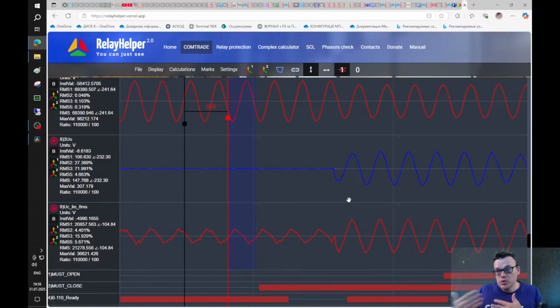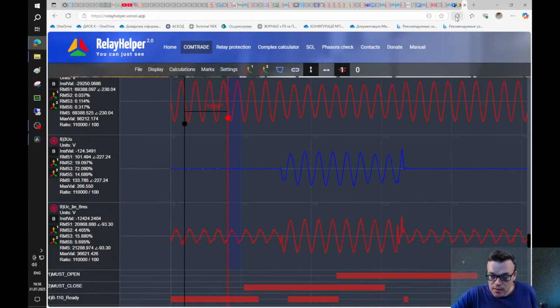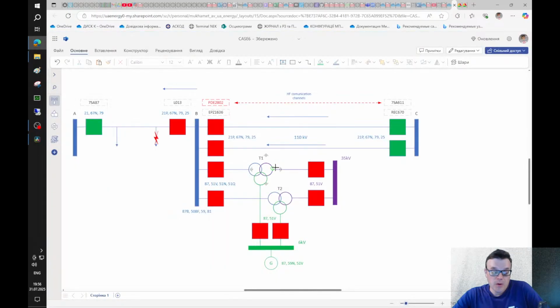So after that we should understand that we must set this setting below that point. That was one of the problems that we found, and that's why we need to look at our calculation algorithms and what settings should be put in relays for this voltage level if there is some generation.